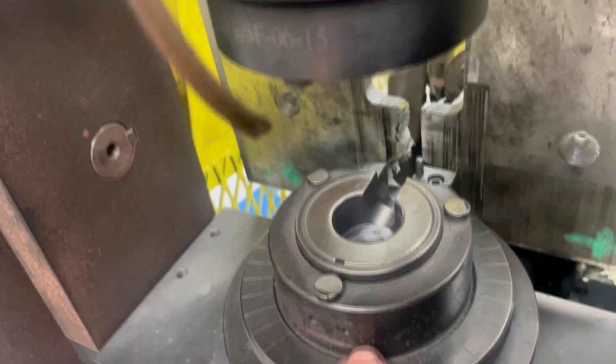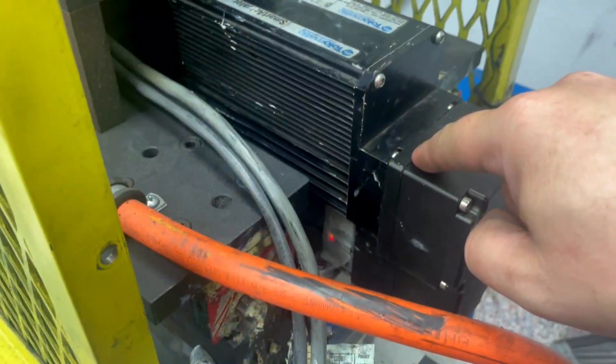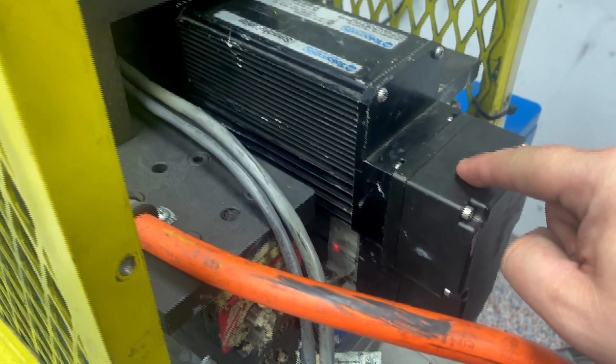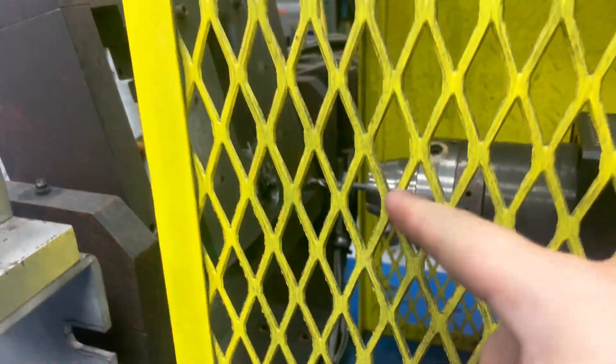Here, we are working on a Mueller Systems ball shaper. This unit cuts, via a spindle inside the housing, spherical shapes out of plastic. Here, we have a table that is controlled by a Tolomatic servo motor, which is our problem. It faults out when the table tries to move back and forth and move the piece into position at the spindle head.